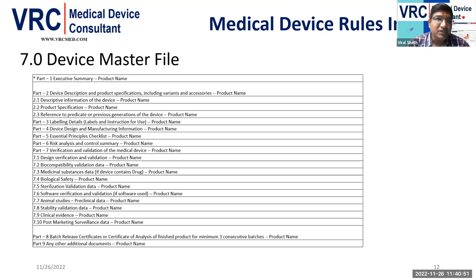We can see the executive summary, device description, and product specifications, including variants and accessories, descriptive information of the device, and reference to a predicate. You should identify any device already approved by the CDSCO and compare your device to that previously approved device in terms of technology, mechanism, make, and indication for use, so you can claim your device is substantially equivalent to the already cleared device.